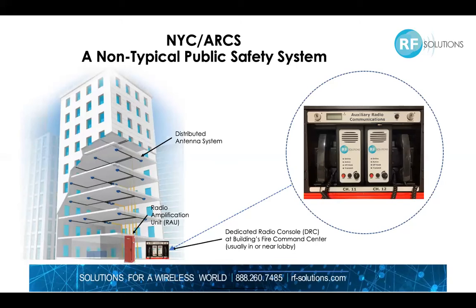Every building has a designated fire command center, where a dedicated radio console, or DRC, is installed. Upon arriving at a building, FDNY activates the ARC system from this console using their elevator control key. This triggers the system, amplifying signals from firefighters' portable radios and retransmitting them throughout the building. There are additional control capabilities available at the console. This concept is designed to support teams of firefighters operating simultaneously in a high-rise building.